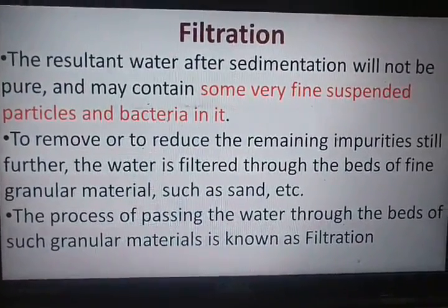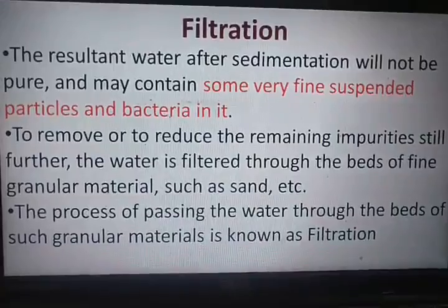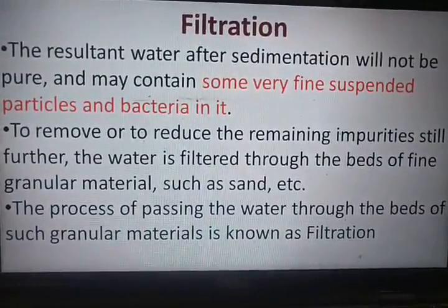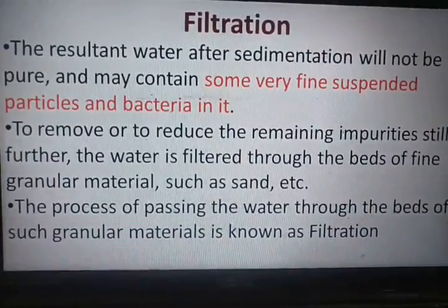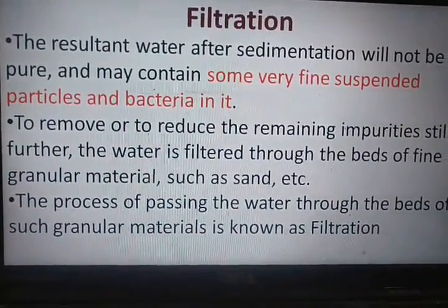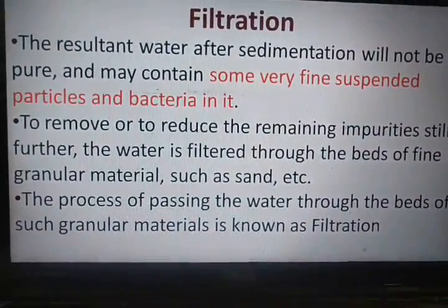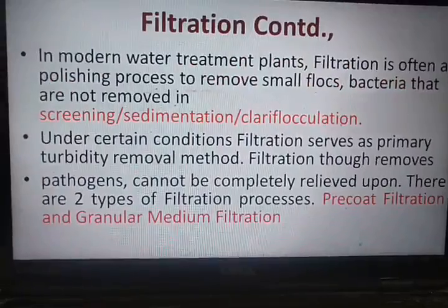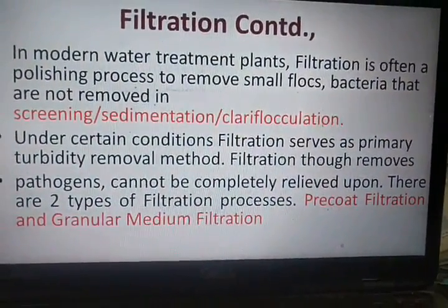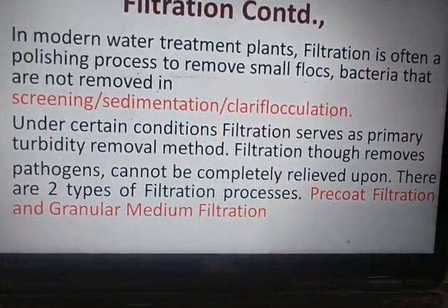The filter material is usually sand and gravel, however nowadays some synthetic materials are also used as filter media. Filtration accordingly is the process of passing the water through beds of such granular material. In modern water treatment plants, filtration is often a polishing process to remove small flocs and bacteria that are not removed in the previous treatment units.